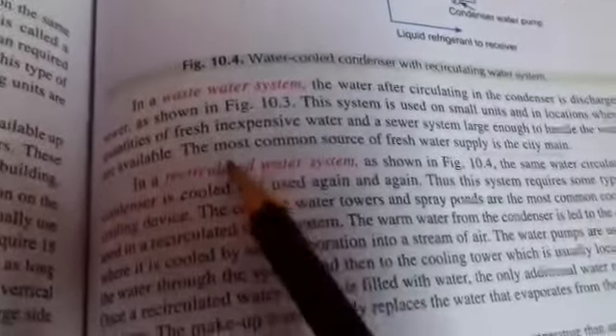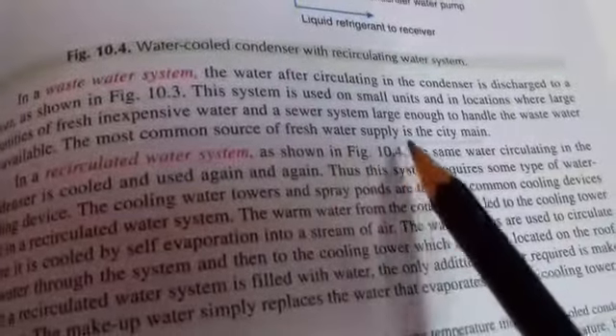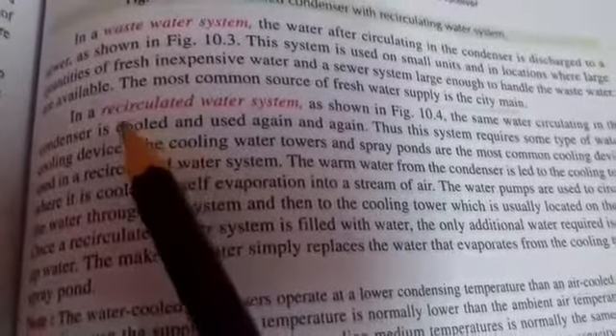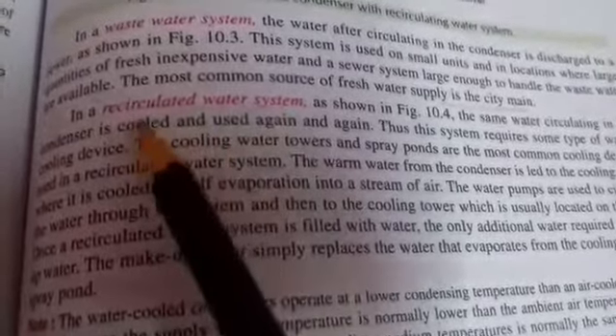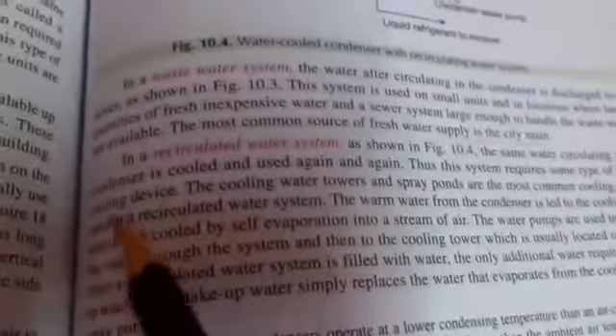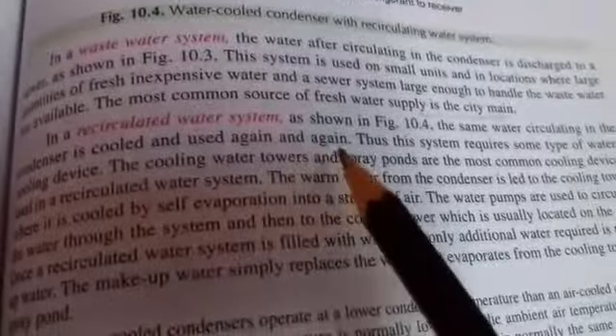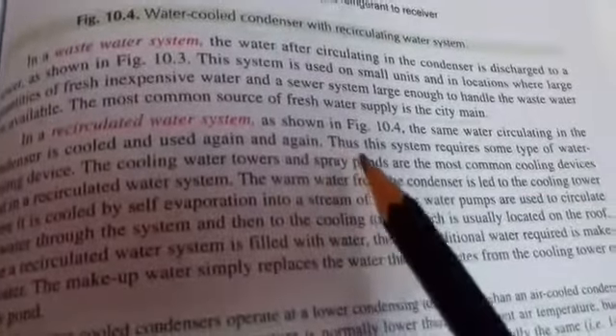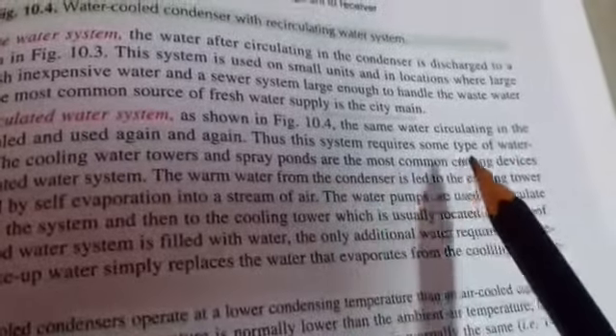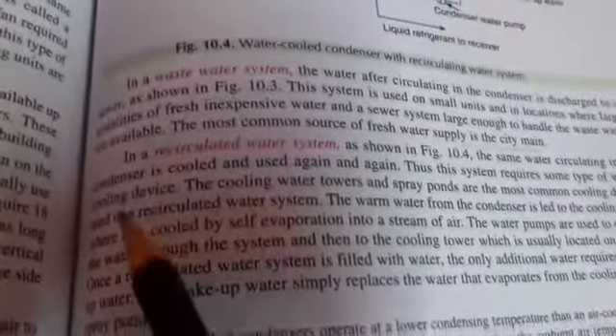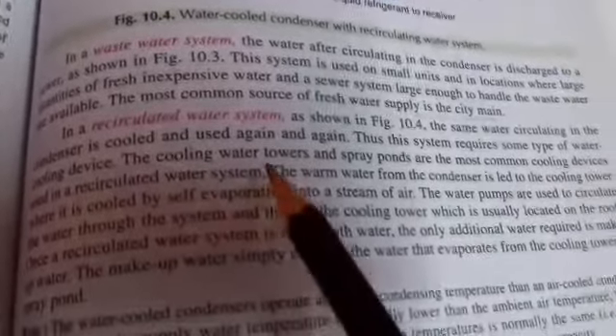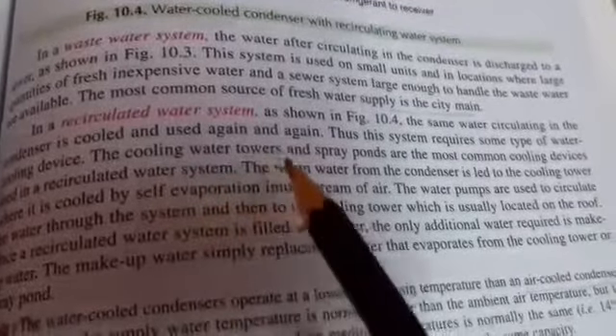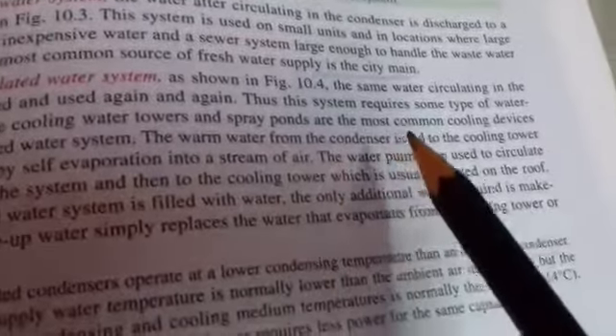The second type of recirculating water system, that the second type of condenser cooling system shown in the figure I have shown you. The same water circulating in condenser is cooled and used again and again. Repeatedly it is being used. Thus, this system requires some type of water cooling device. The cooling water towers and spray pond are the most common cooling device used in recirculated water system.